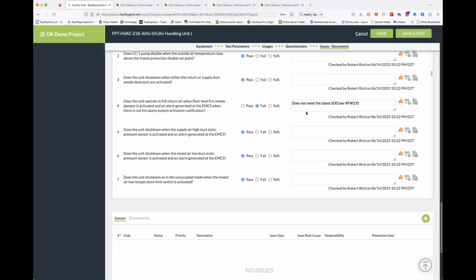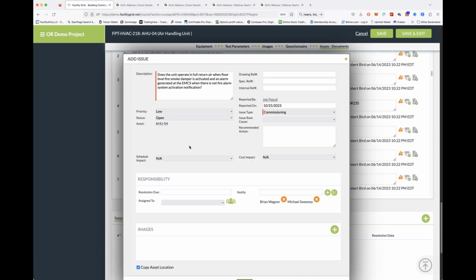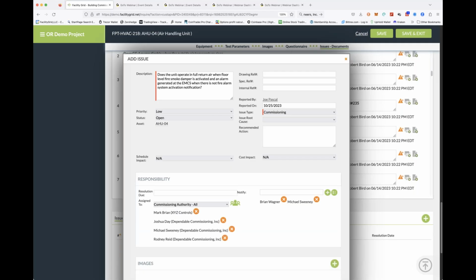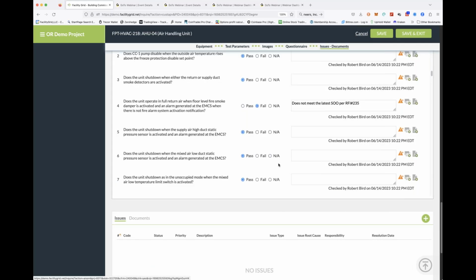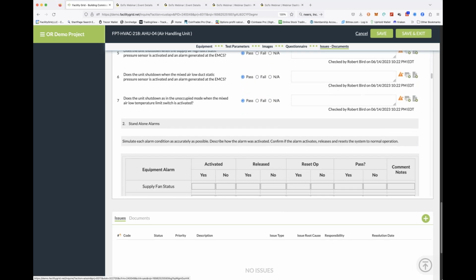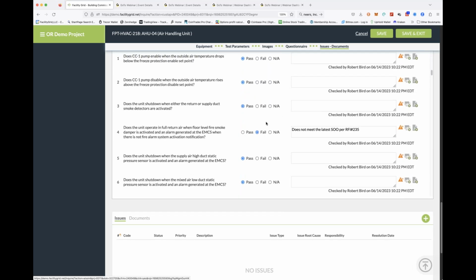This particular item does not meet the sequence of operations per the RFI. That's documented. He could also create an issue here, easily assign that responsibility back to the commissioning authority so they're aware we need an edit on this test. That would all be recorded, and it hasn't interfered with the commissioning authority's process. This just makes it very easy for your team to review the test in advance and then communicate to the commissioning authority, which, by the way, they love.